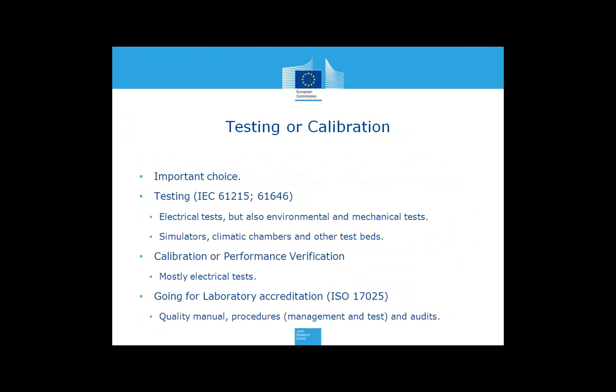Calibration: the question is calibration or performance verification. These are mostly electrical tests, so the determination of the output power versus the incoming light. And one question everybody has to ask himself is: are we going for accreditation? Laboratory accreditation, according to ISO 17025, requires a quality manual, procedures, management, and test procedures, and of course audits. You have to submit yourself to external audits, and you have to perform internal audits.